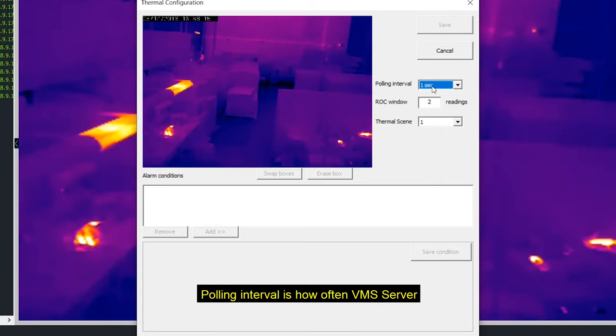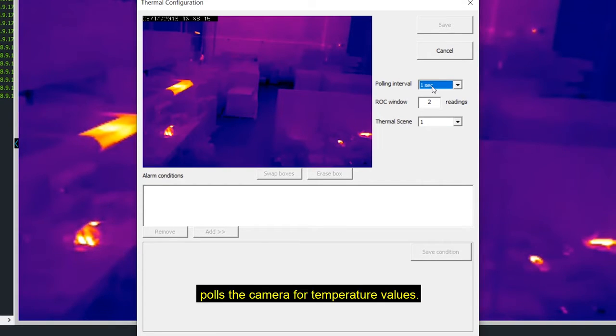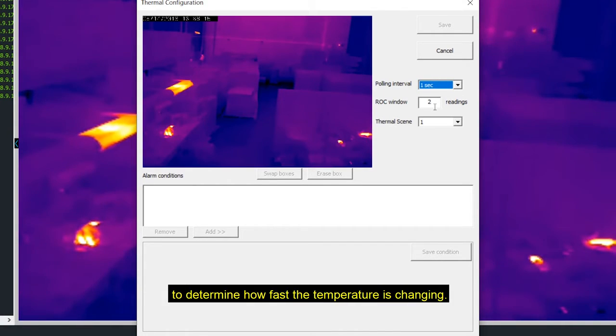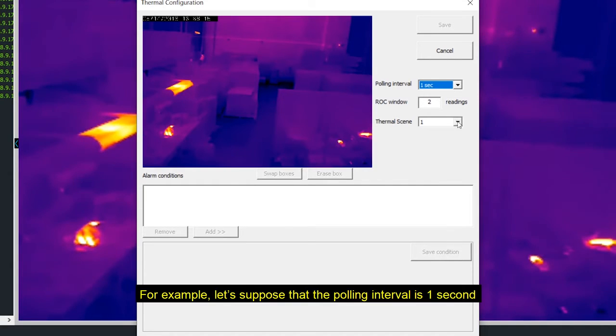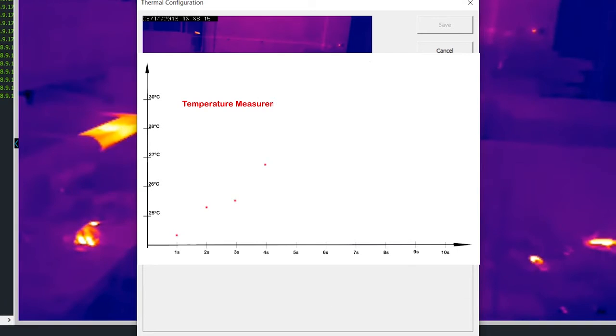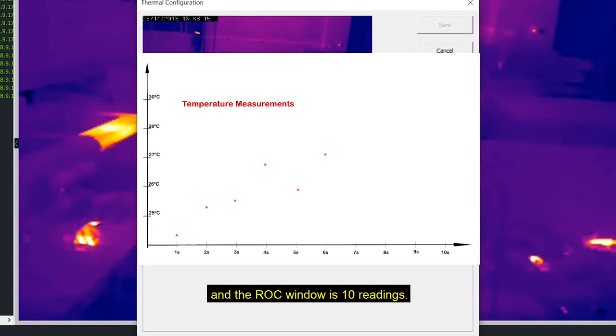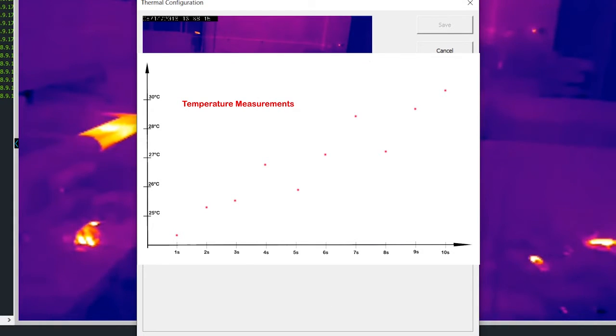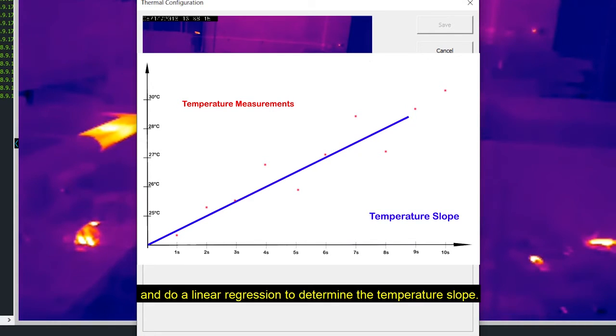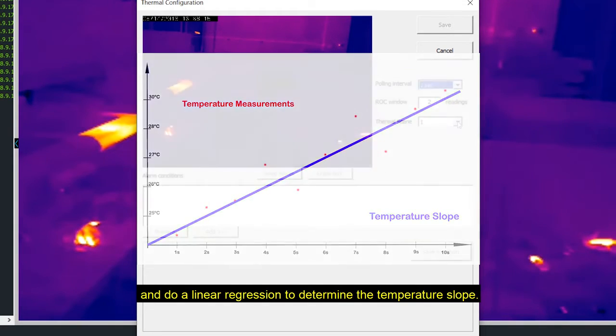At the right we have three parameters to set up. Polling interval is how often VMS server polls the camera for temperature values. ROC window is the rate of change window to determine how fast the temperature is changing. For example, let's suppose that the polling interval is one second and the ROC window is 10 readings. The software will take 10 measures, one per second, and do a linear regression to determine the temperature slope.